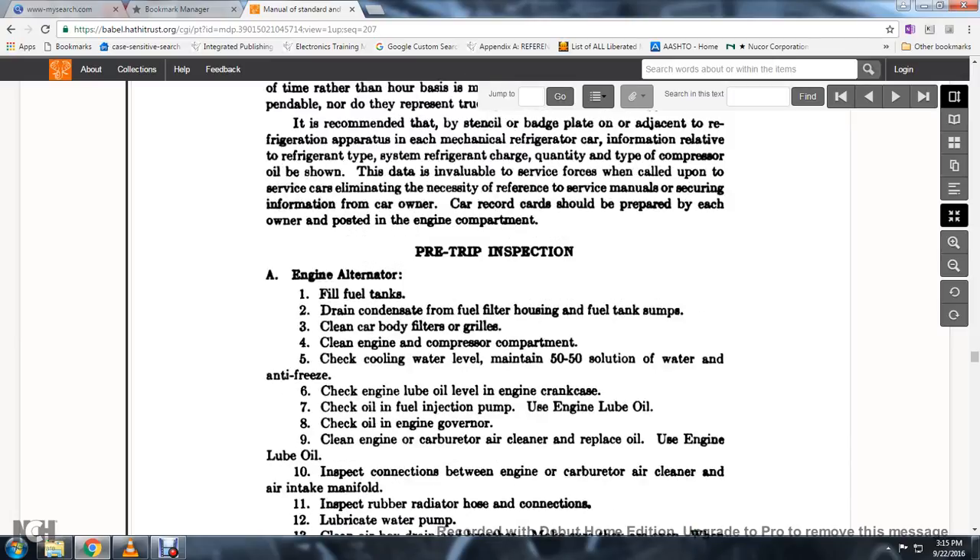Pre-trip inspections. Engine alternator: fill the fuel tanks, drain the condensate from the fuel filter, clean the oil and air filters, clean car body filtering grills, clean engine compressor compartment, check the cooling water and maintain a 50-50 solution of water and anti-freeze, check the engine lube oil for the engine crankcase, check oil in the fuel injection pump using engine lube oil, check oil in the engine governor, clean the engine carburetor air cleaner, and replace the oil using engine lube oil.